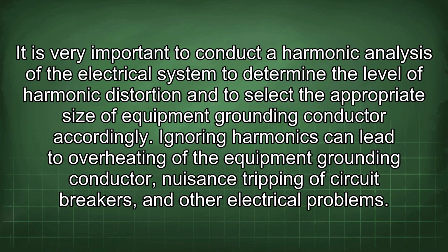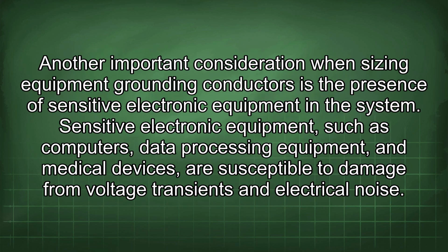It is very important to conduct a harmonic analysis of the electrical system to determine the level of harmonic distortion and to select the appropriate size of equipment grounding conductor accordingly. Ignoring harmonics can lead to overheating of the equipment grounding conductor, nuisance tripping of circuit breakers, and other electrical problems. Another important consideration when sizing equipment grounding conductors is the presence of sensitive electronic equipment in the system. Sensitive electronic equipment, such as computers, data processing equipment, and medical devices, are susceptible to damage from voltage transients and electrical noise.